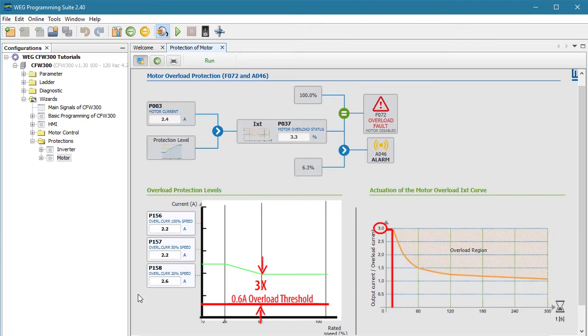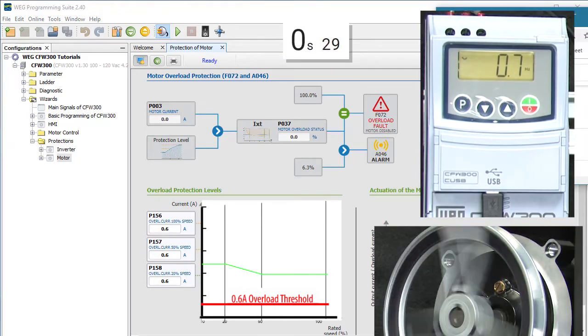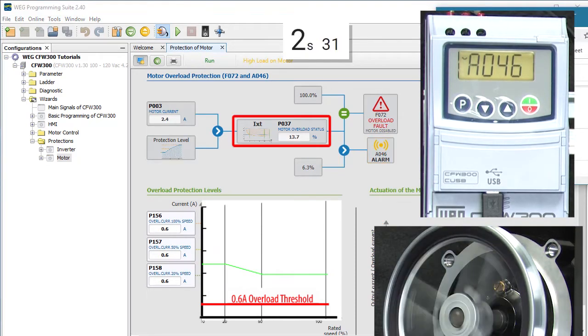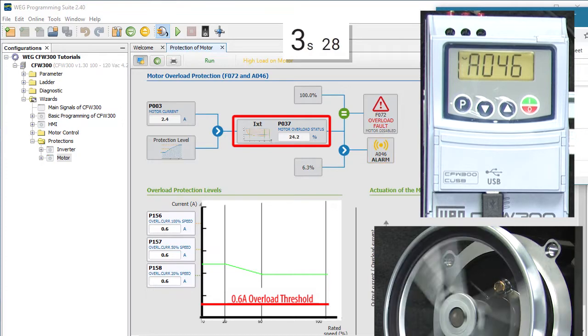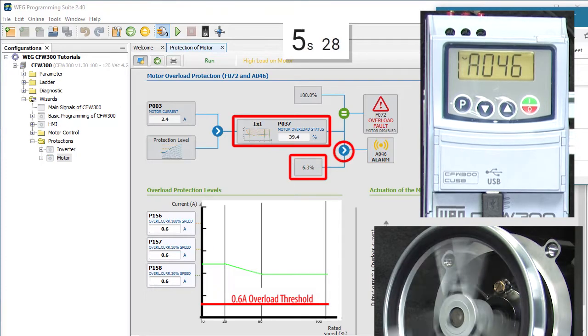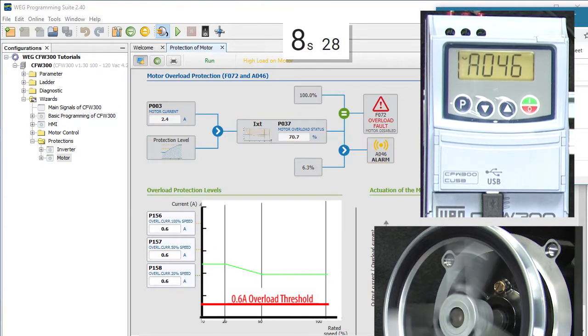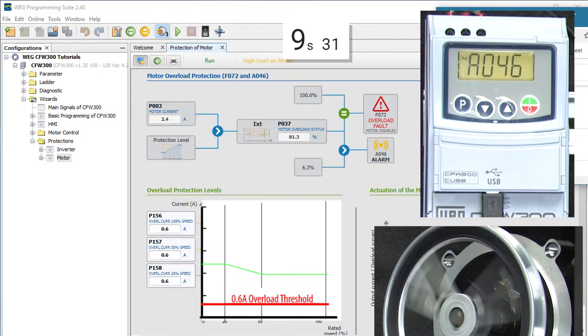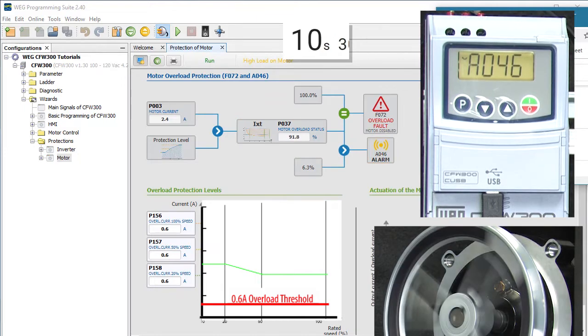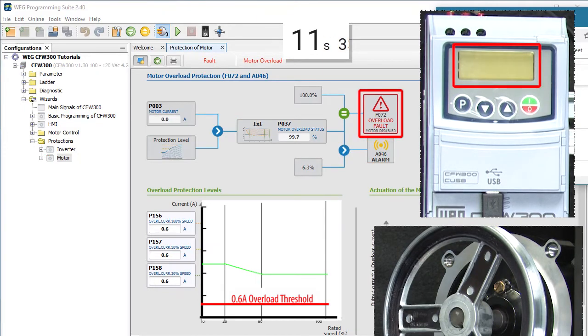Well, let's see. I'll hit run and look — we see the IXT integrating up. It already passed 6.3% so we have an alarm on the drive. And when it hits 100% — bingo! We get a fault and the drive shuts down its output in about 11 seconds. Perfect.